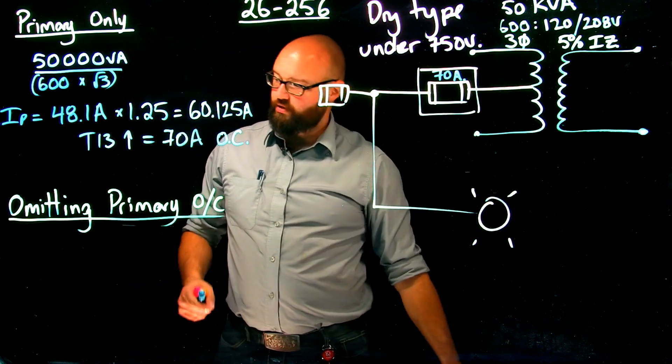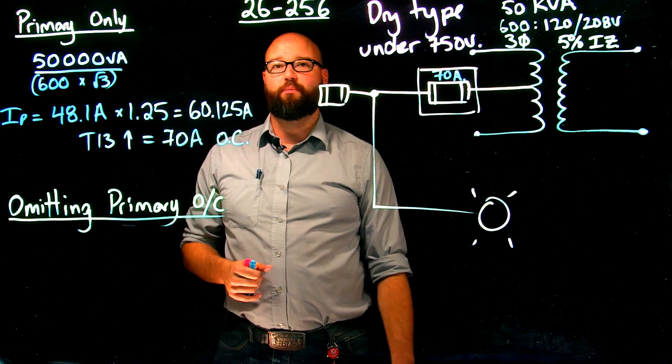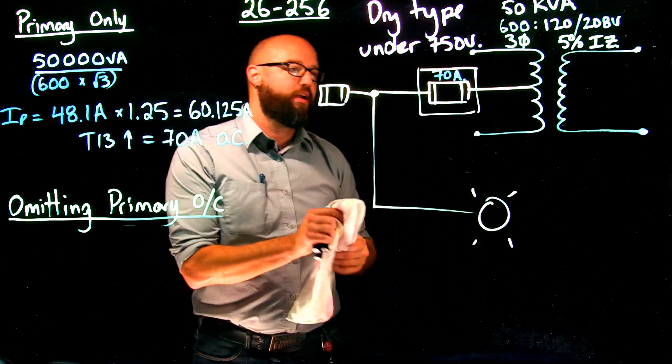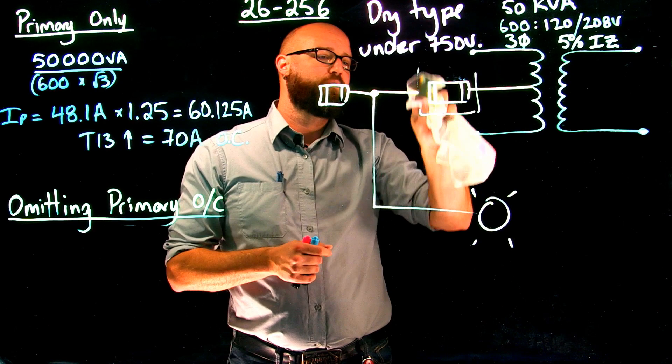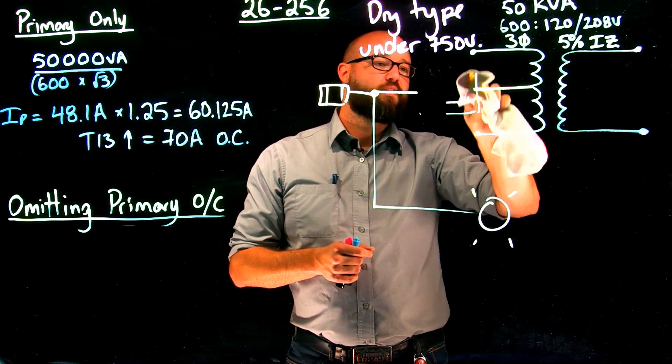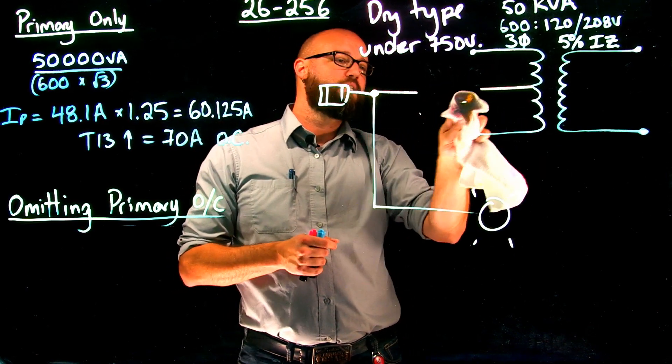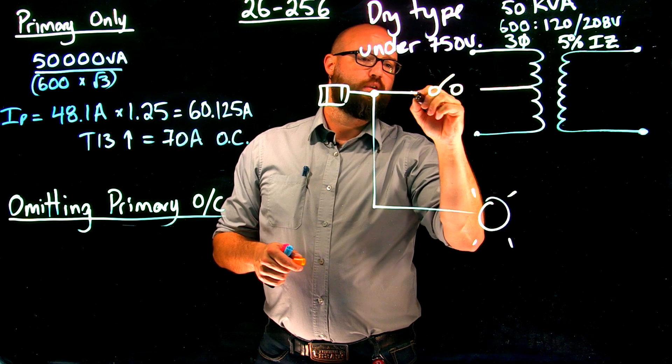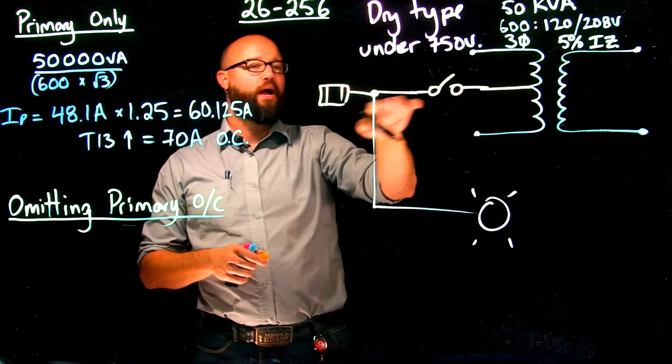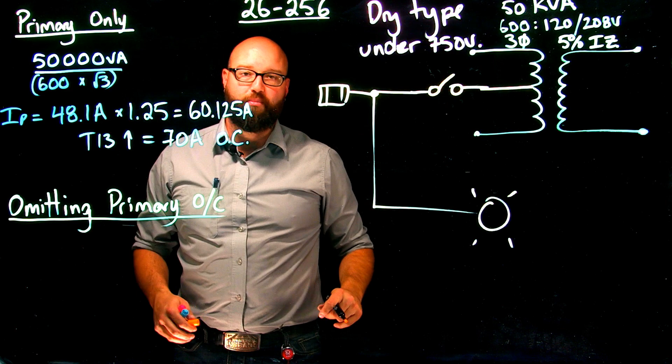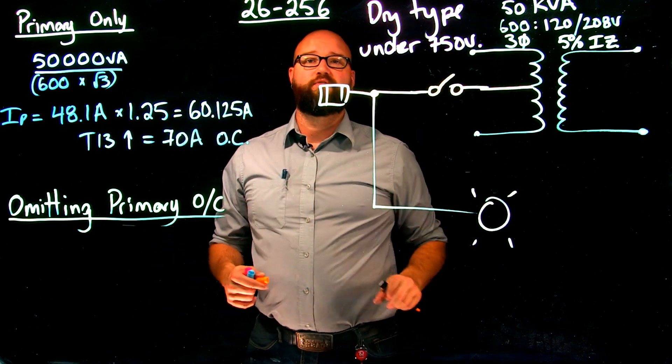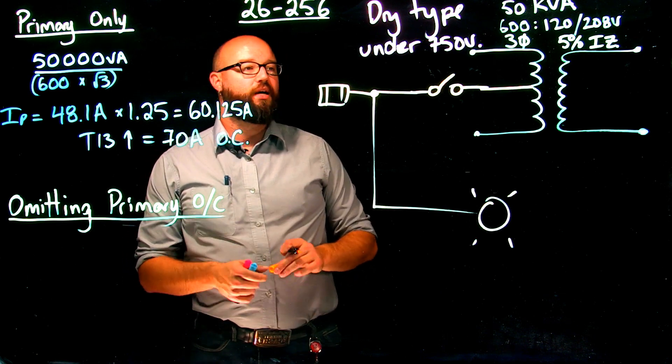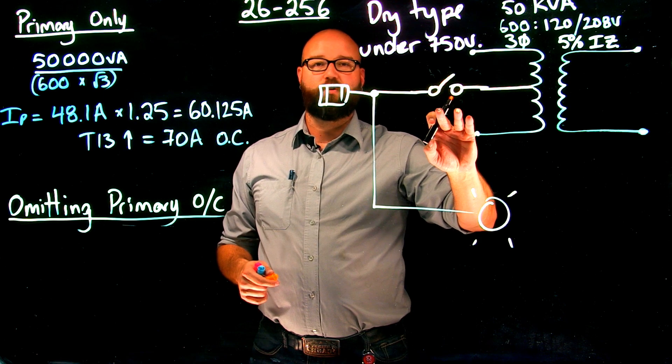So if we move to omitting our primary overcurrent, just like in the previous video, if I was to remove this primary overcurrent, we're going to get rid of that right now. 26-250 tells me, again, I still have to have some type of disconnecting means in here. Maybe it's, again, we'll just use an unfused disconnect. We want to know what happens if we get rid of that primary, or are we allowed to get rid of that primary? We are, according to subrule 2, 26-256, and it gives us the actual multipliers right in the rule. Subrule 2 tells me that if we are going to omit primary protection, which we're allowed to do, I must have a secondary overcurrent.